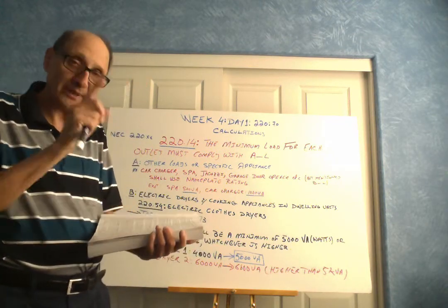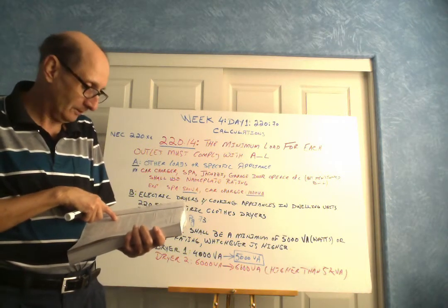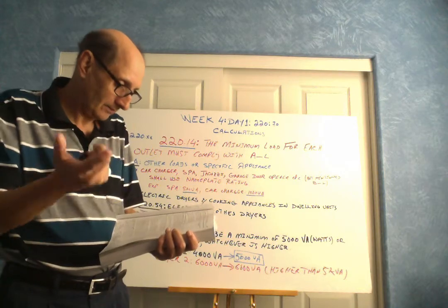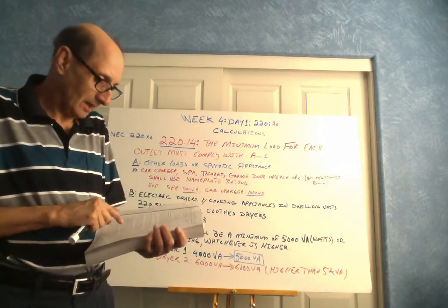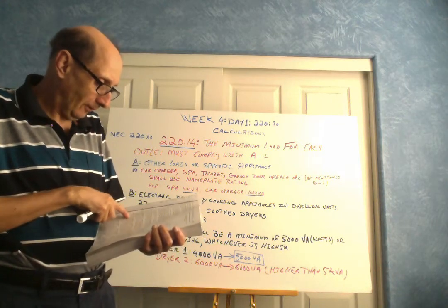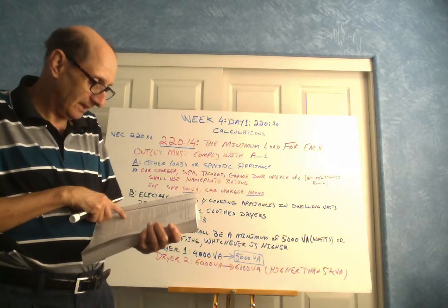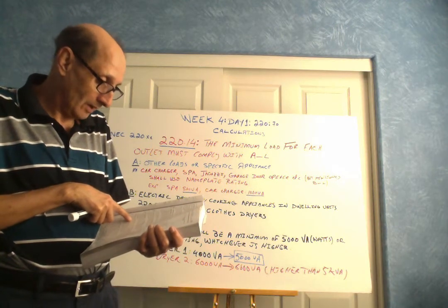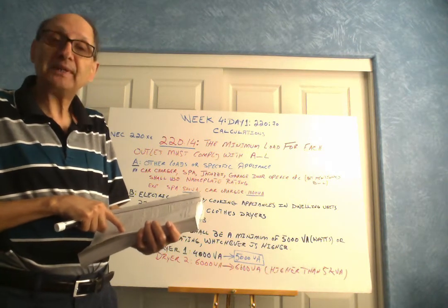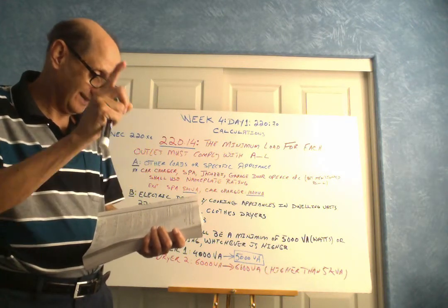So on page 73, let's turn to section 220.54, electric clothes dryers, dwelling units. Okay, wherever you reside, live. I'm going to read and then go back over here. It says, the load for household electric clothes dryers in a dwelling unit or units shall be either 5000 watts, in parentheses volt amps, or the nameplate rating, whichever is larger for each dryer served.